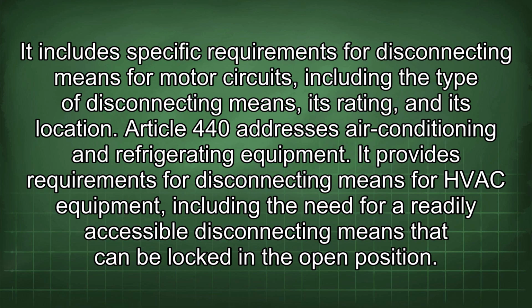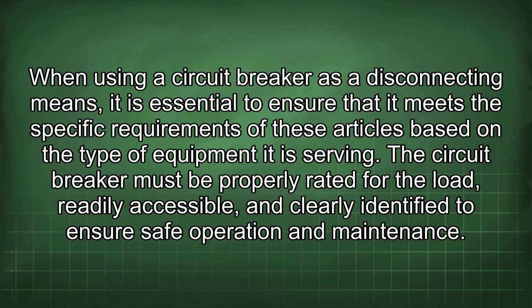It provides requirements for disconnecting means for HVAC equipment, including the need for a readily accessible disconnecting means that can be locked in the open position. When using a circuit breaker as a disconnecting means, it is essential to ensure that it meets the specific requirements of these articles based on the type of equipment it is serving. The circuit breaker must be properly rated for the load, readily accessible, and clearly identified to ensure safe operation and maintenance.